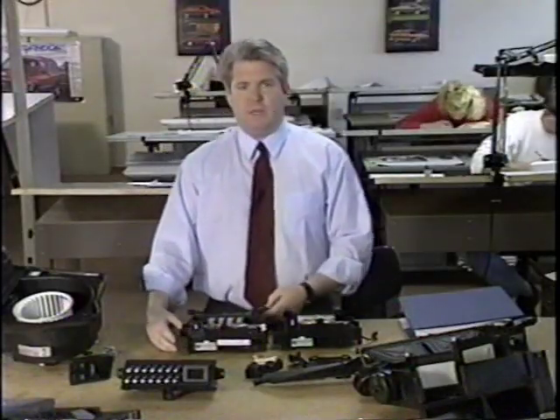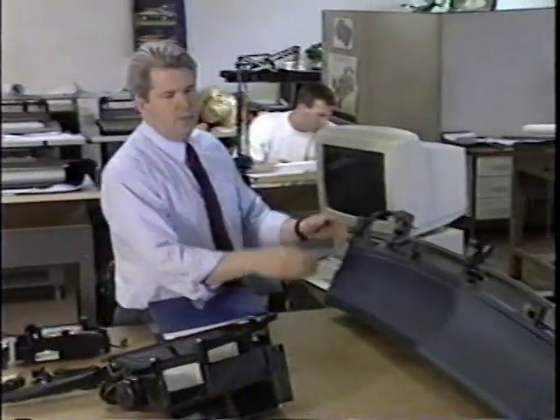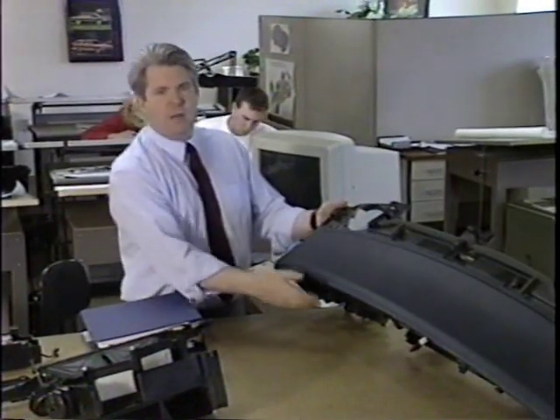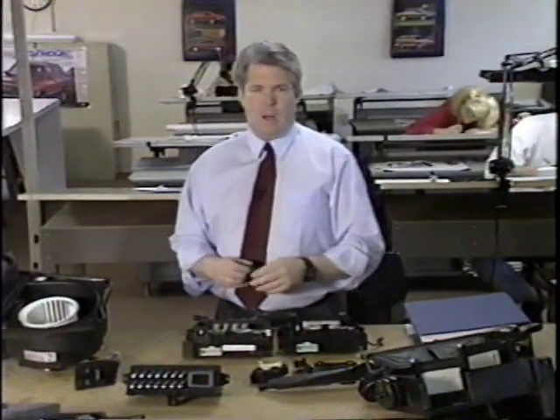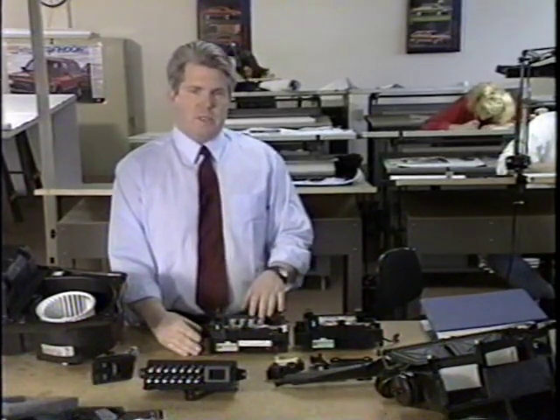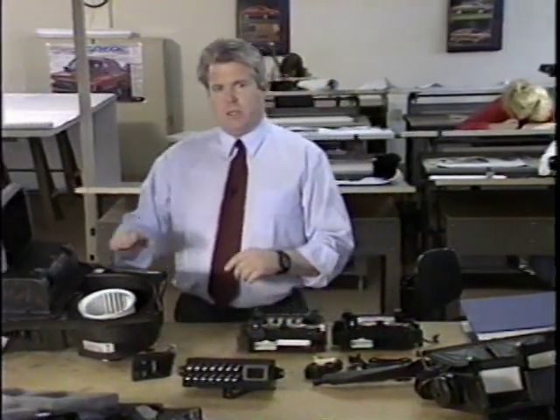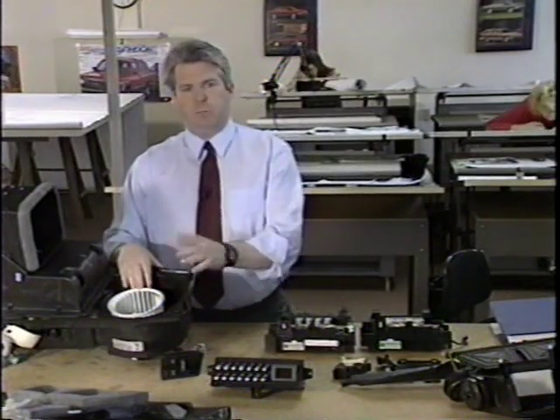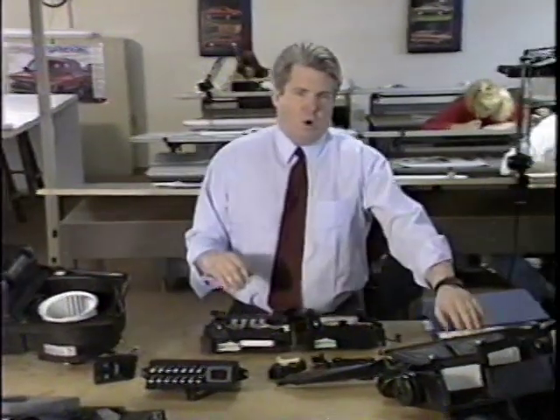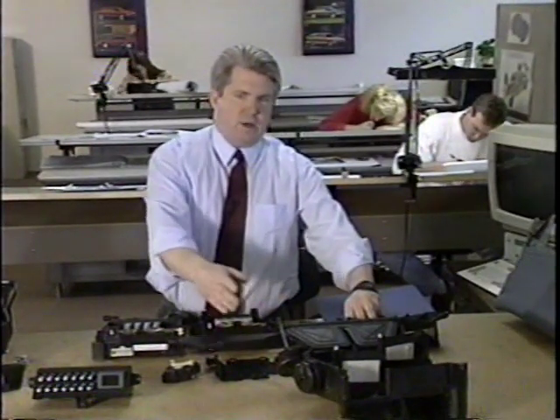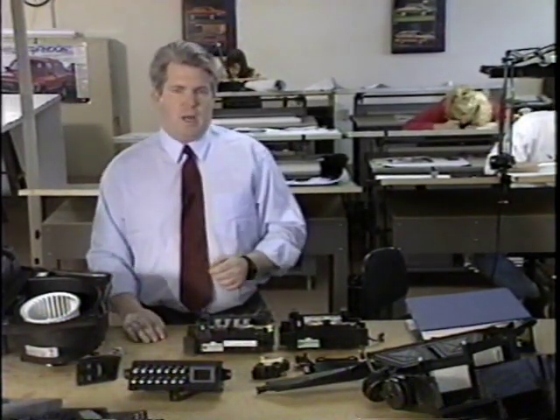The programmer receives input from the driver and passenger control heads, the right and left solar sensors, the in-vehicle temperature sensor, the ambient sensor, and the powertrain control module. A microprocessor in the programmer processes signals from these inputs and then sends a voltage signal to the blower module to adjust blower motor speed, open the vacuum actuated valves that direct air to the desired locations, or sends a voltage signal to the driver and passenger air mix valves to adjust the temperature setting.